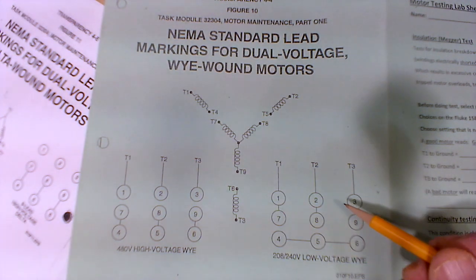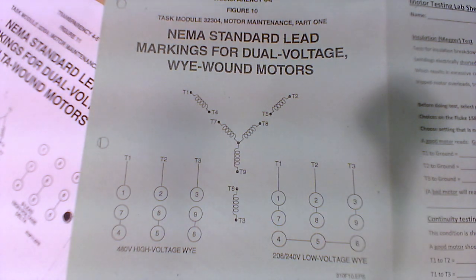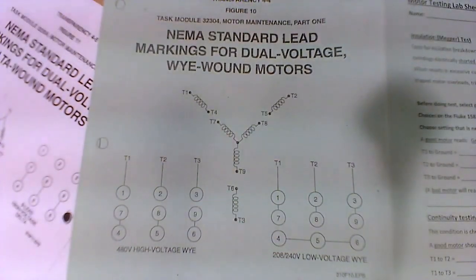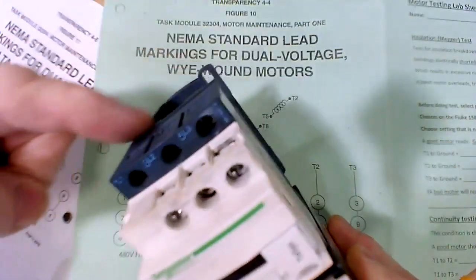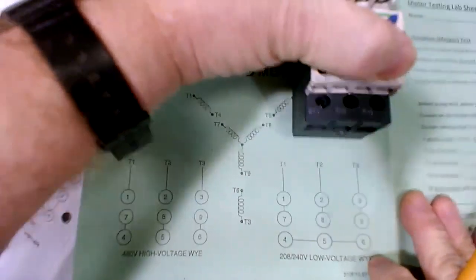So here's how you do it with the wire nuts. You come from the motor starter. Let me grab a starter real quick. So you have the motor starter right here. The 3 phases come into the starter here, on L1 through L3, and then they leave on T1 through T3. So they leave here, and picture it right here. But you've got the starter.